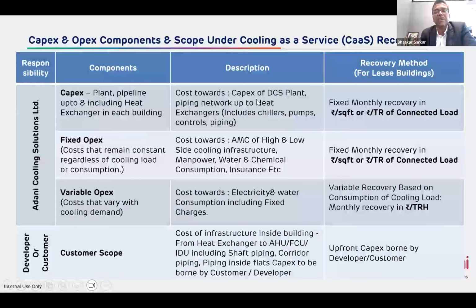The capex is charged to the end users, which includes the cost of the DCS plant, the piping and heat exchangers, etc., all the equipment, chillers, pumps, cooling towers, control equipment, piping, etc., which is normally charged through a fixed monthly recovery on rupees per square feet or rupees per TR of connected load. The fixed OPEX is also charged on rupees per TR, or sometimes it can also be charged on rupees per TRH on the basis of actual pay per use. And the variable cost is necessarily charged on a rupees per TRH. Now, inside the flat, the customer or the developer gets it done, the shaft piping, corridor piping, and the inside flat infrastructure. However, we do the O&M of that.